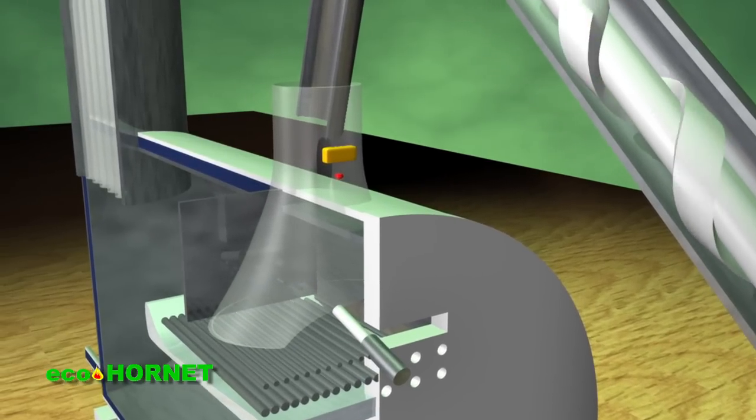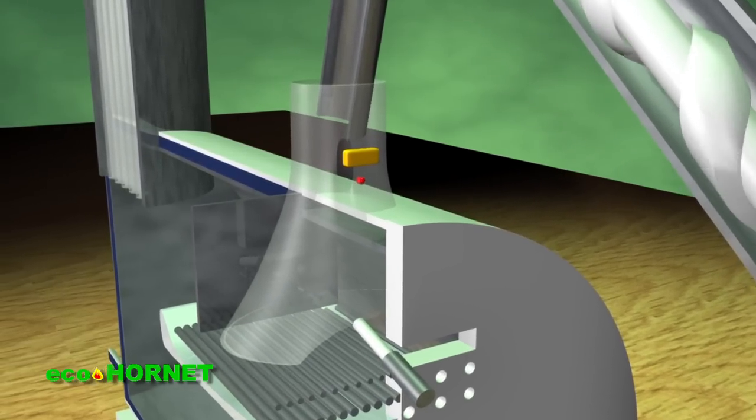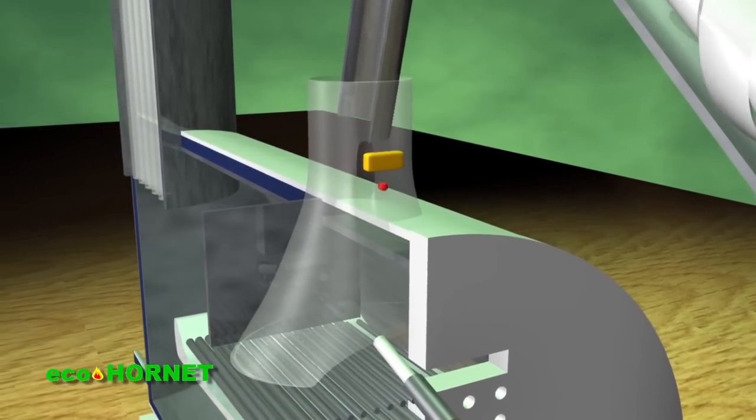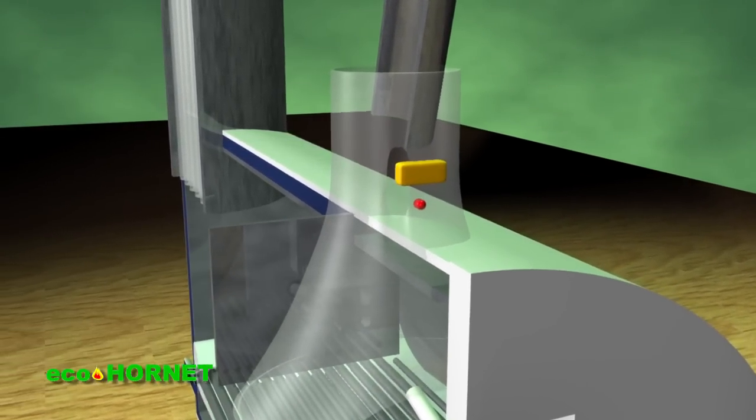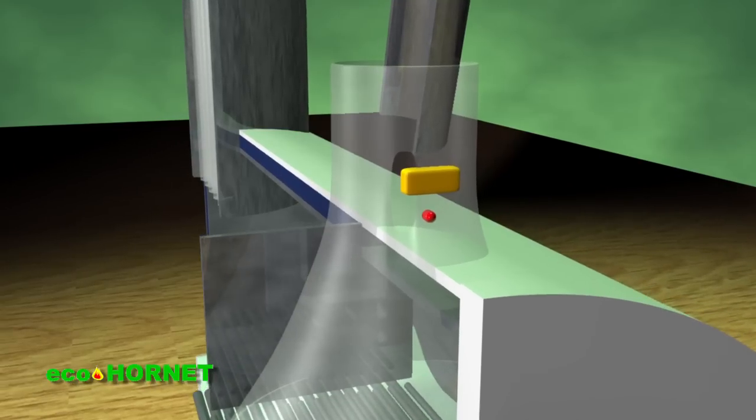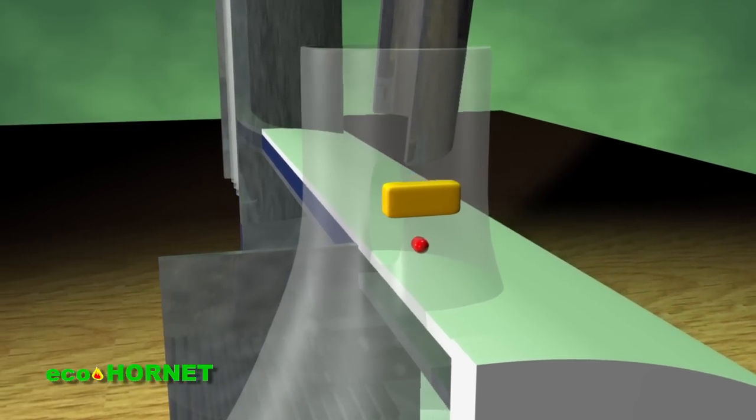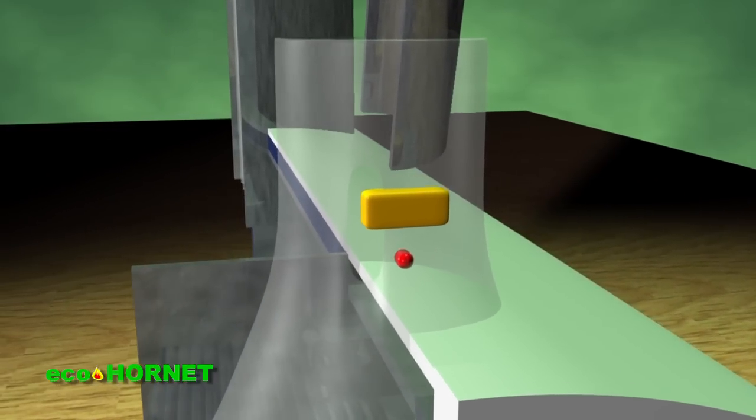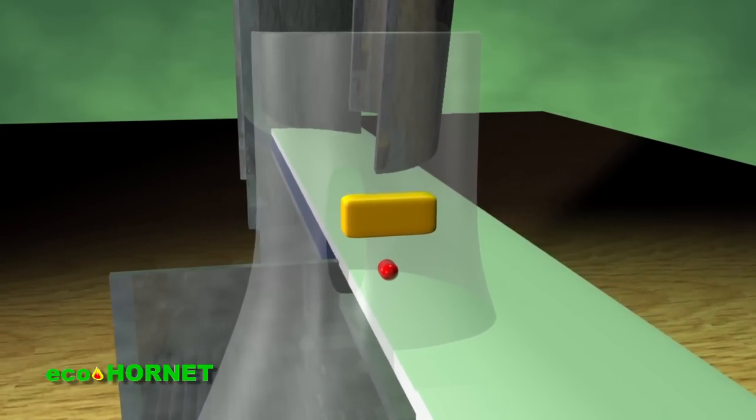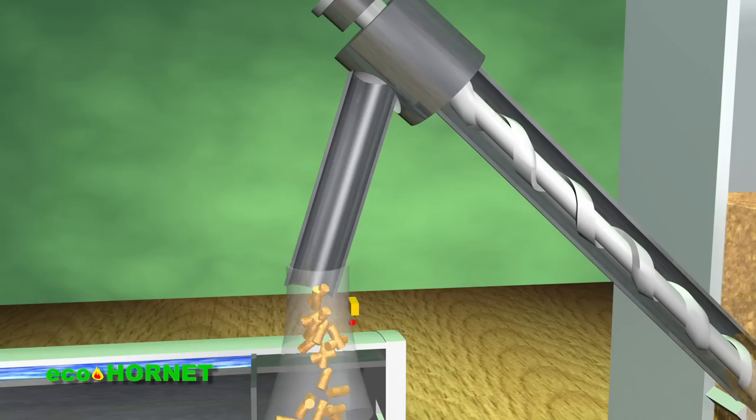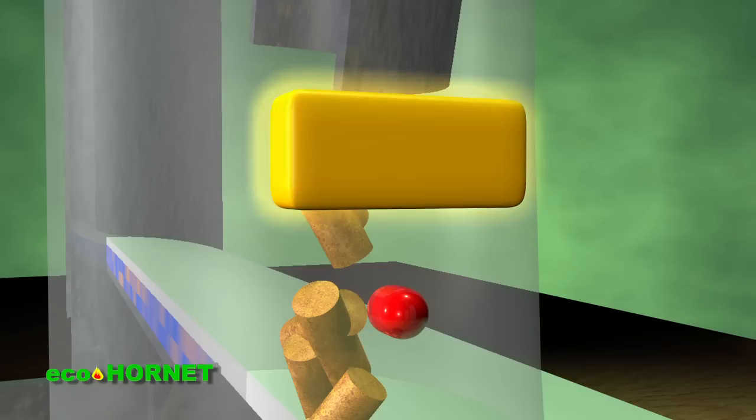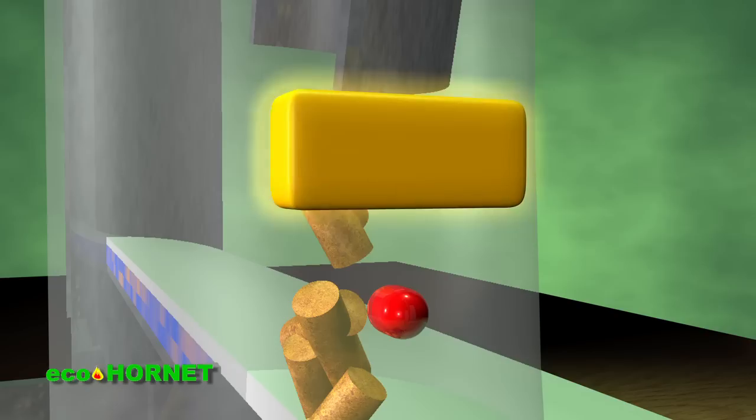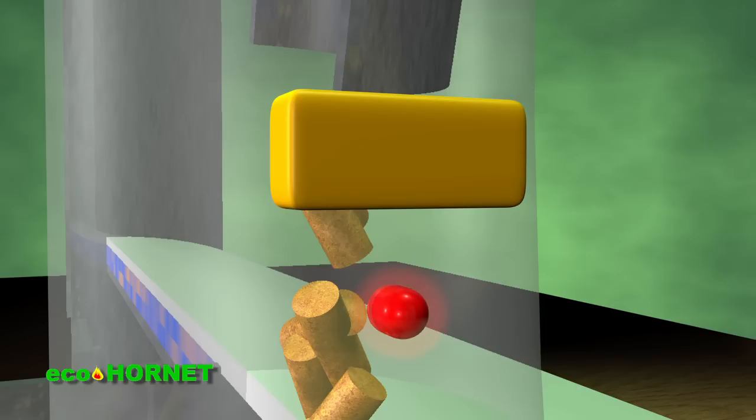The pellet level in the combustion chamber is measured by a level sensor that maintains a constant fuel level above the grate and keeps a pellet-free area at the supply tube level, preventing flame spread to the worm gear and bunker. The level sensor is protected by placing it on a flame retardant wall made of glass textilite and by a temperature sensor that interrupts feeding when 60 degrees Celsius is reached on the metal pipe surface.